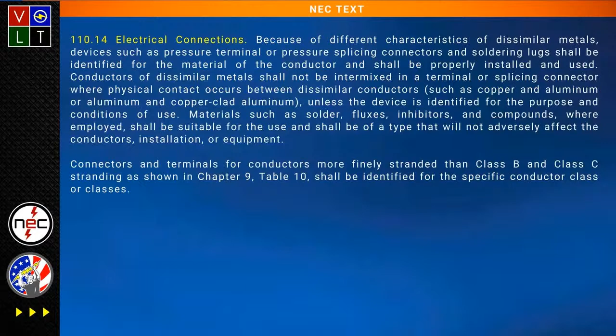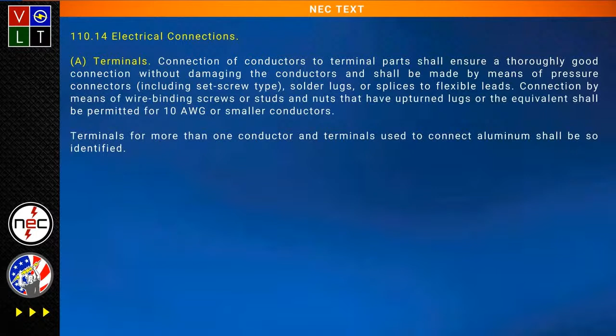I wouldn't have even thought about 110.14, to be honest. When I was doing the myth of the week, I was thinking about 110.3B, but you're correct, this absolutely applies, because if you're not reading the manufacturer instructions, you could have dissimilar metals and all kinds of things causing deterioration of your connection, which leads to heat and carbon buildup, and then failure on that connection.